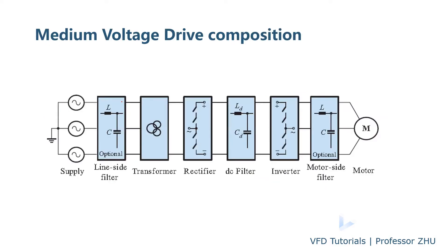This is a typical composition of a medium voltage drive. We have the rectifier, which converts AC to DC, and DC filter which uses a capacitor or reactor. Then the inverter, DC to AC. And sometimes on the motor side you have a filter. Also, most of the medium voltage drive you have a transformer in the input side, and sometimes you need a line-side filter. And here is the power supply.